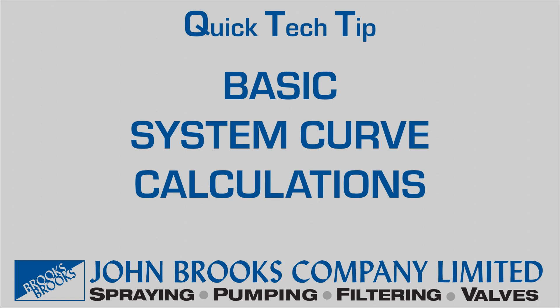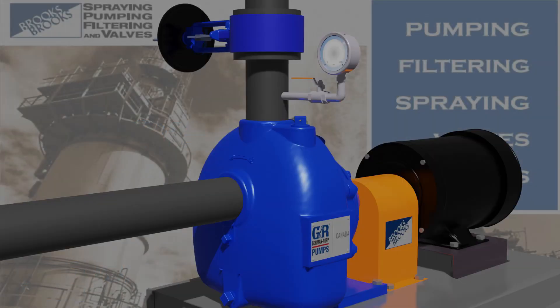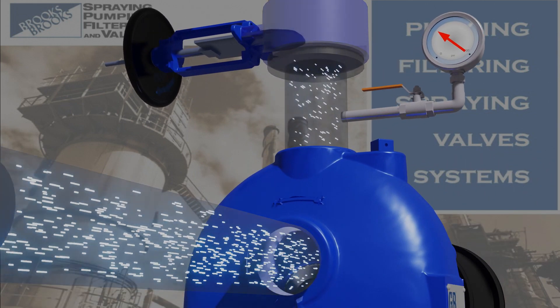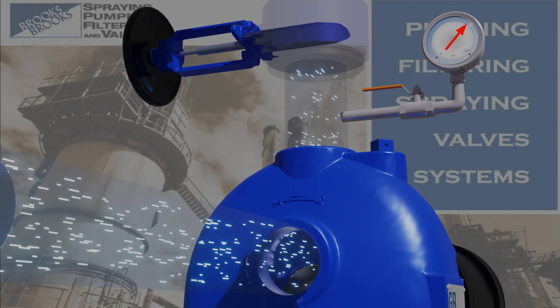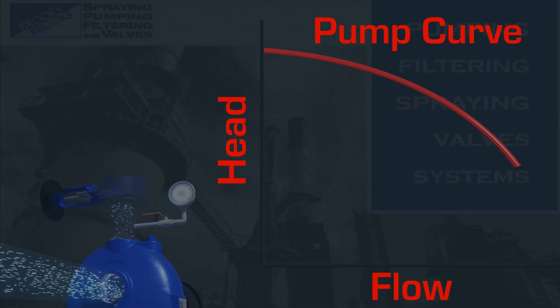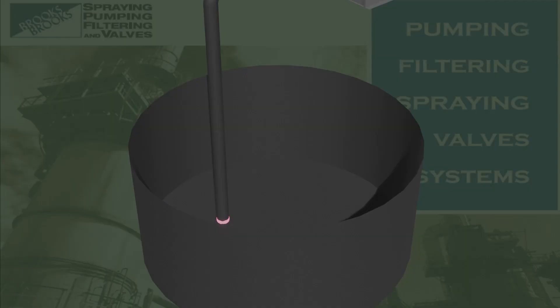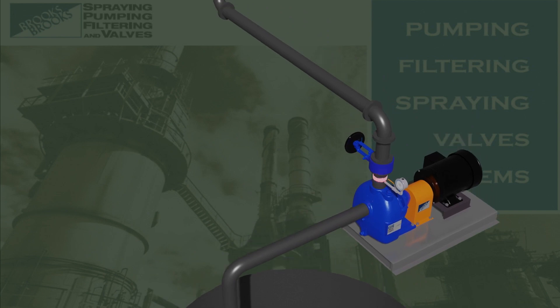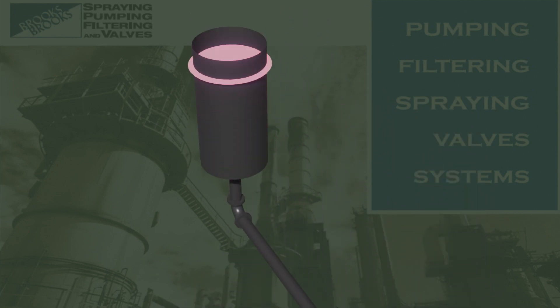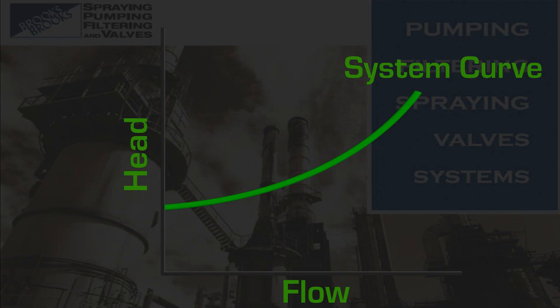Quick tech tip: basic system curve calculations by the John Brooks Company. All pumps have some kind of relationship between their ability to develop flow and the pressure or head that has to be overcome. This relationship, better known as a pump curve, does not by itself tell us what the pump will actually do. In order to predict the pump's operating point, we must first know about the piping system the pump is connected to. Calculating the total pressure drop in a piping system at varying flow rates will give us a system resistance curve.